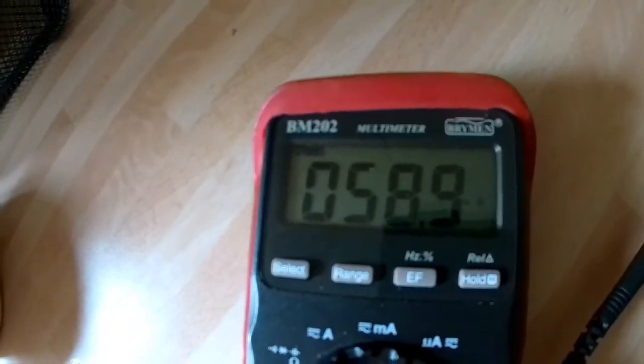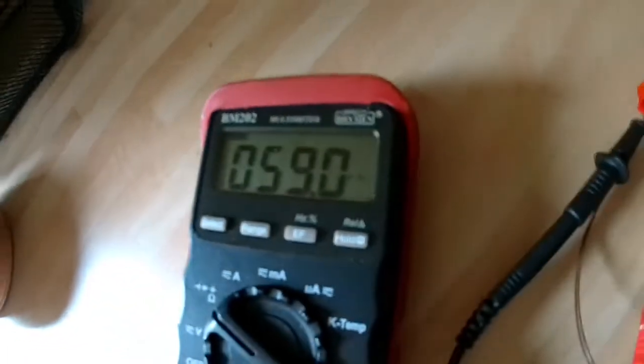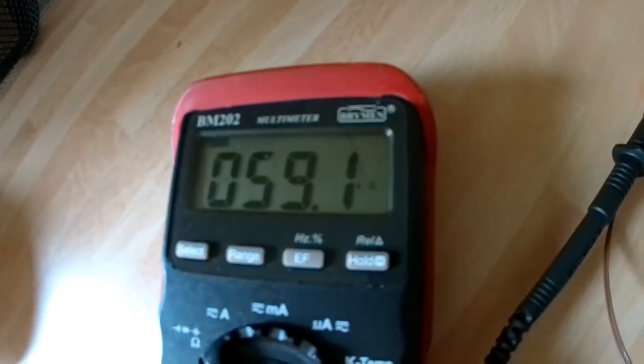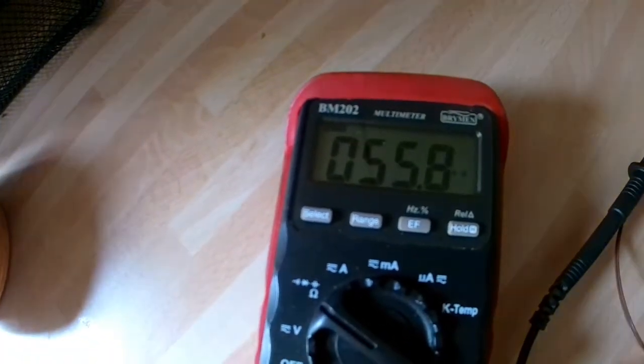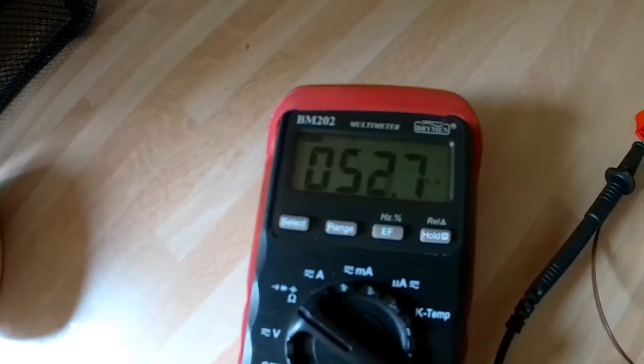You set your meter to the resistance range. Right now you can see that it's reading about 58, 59 kiloohms on the kiloohms range. And if you hold the temperature sensor with your finger on the end of the sensor like that, you will see the reading will go down. See, the resistance is going down.